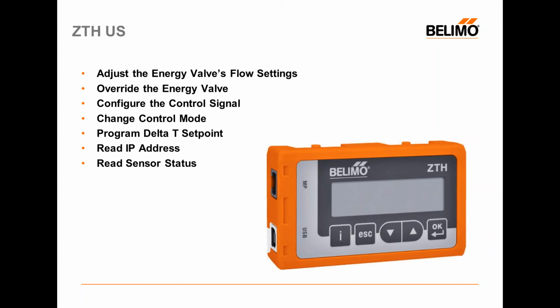You can program delta T set points, see if you've got any sensor failures or issues with your sensors not reading accurately. But one of the things I really like about this ZTH-US, and the thing I use it for most commonly, is if you've got an energy valve where the IP address has been changed, and either it has not been documented or someone has forgotten what that IP address is, the ZTH-US can be used for an IP address discovery.